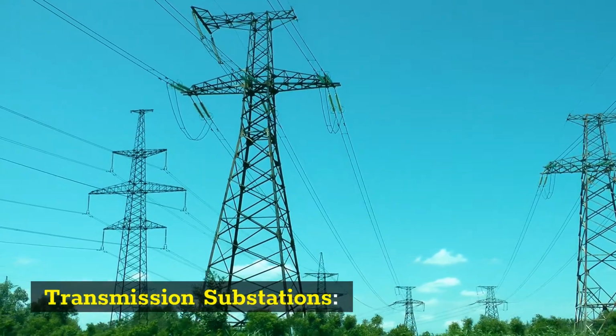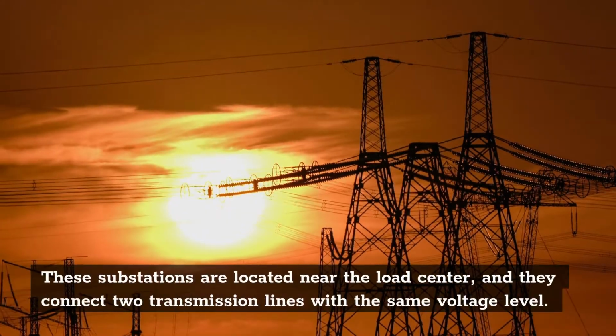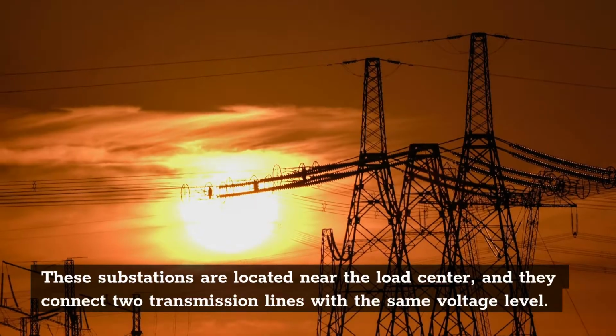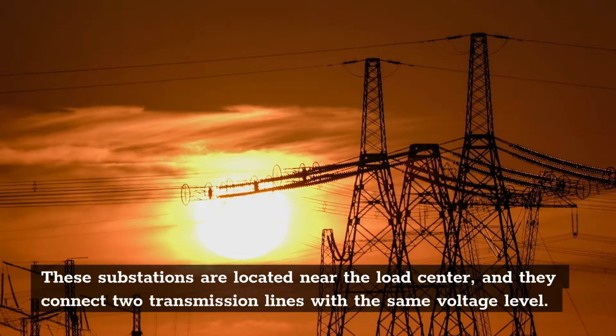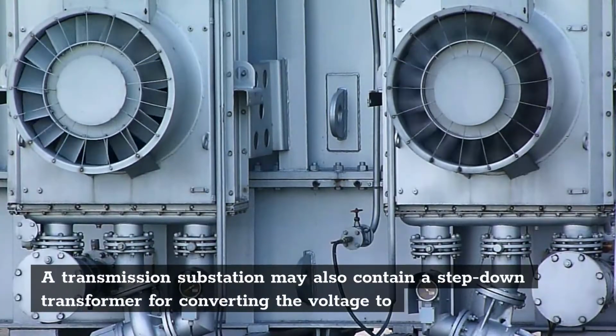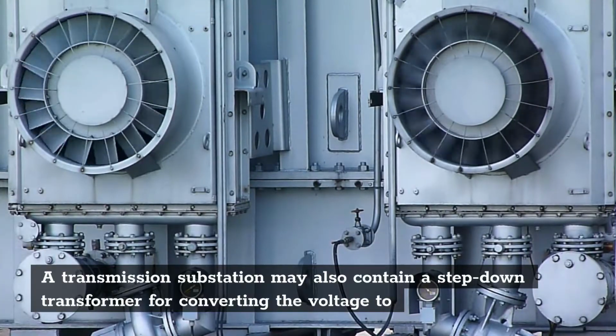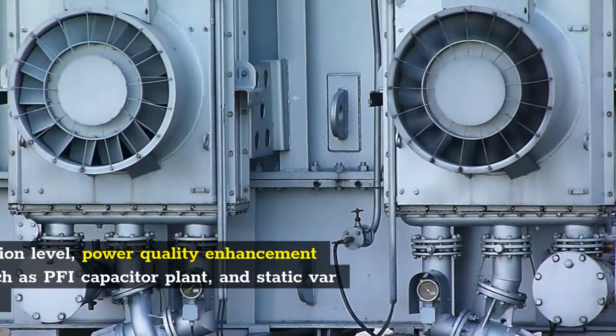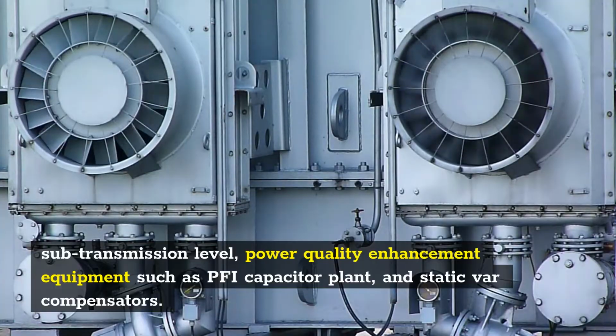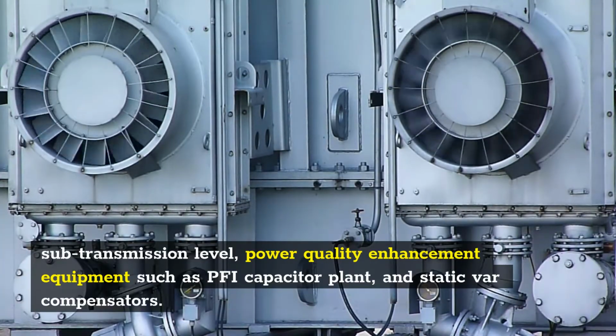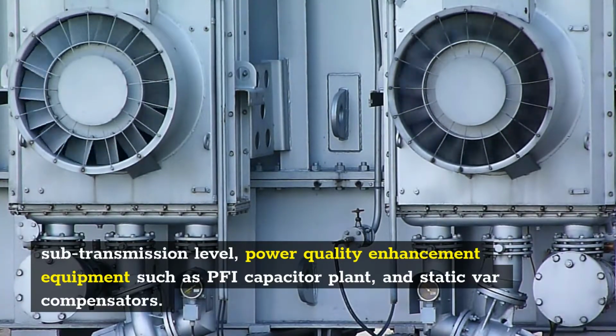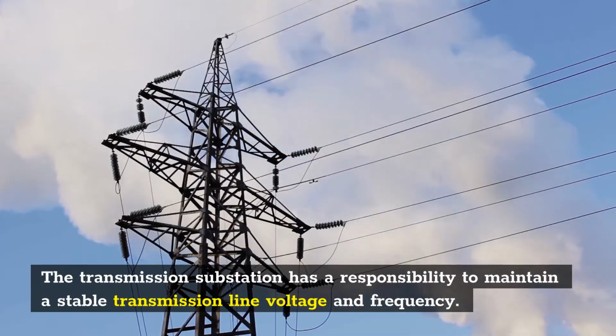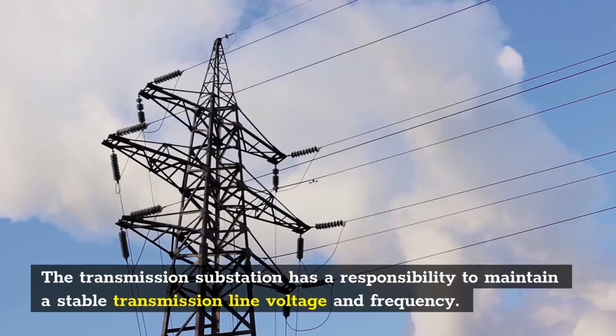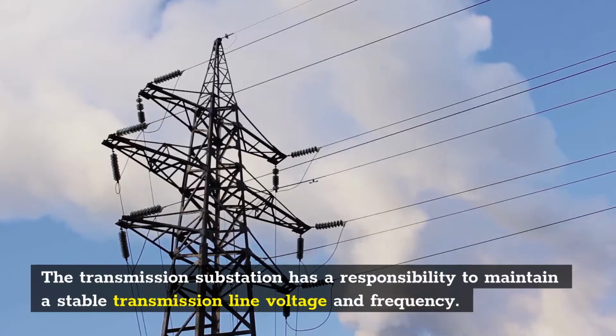Transmission substations. These substations are located near the load center, and they connect two transmission lines with the same voltage level. A transmission substation may also contain a step-down transformer for converting the voltage to sub-transmission level, and power quality enhancement equipment such as PF correction capacitor banks and static VAR compensators. The transmission substation has a responsibility to maintain a stable transmission line voltage and frequency.